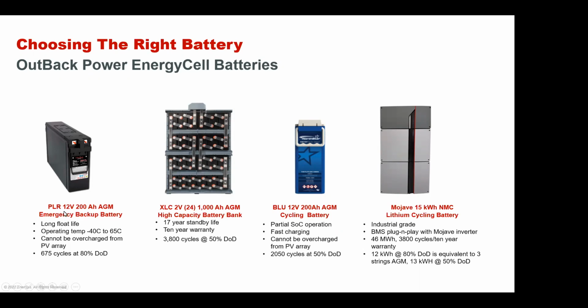This is a great emergency battery backup battery. The blue battery is more of a cycling battery. It has 2,050 cycles at 50% depth of discharge. That's a good off-grid battery because it handles partial state of charge. It likes to live in that. It can be fast charging. And again, it cannot be overcharged from the array.